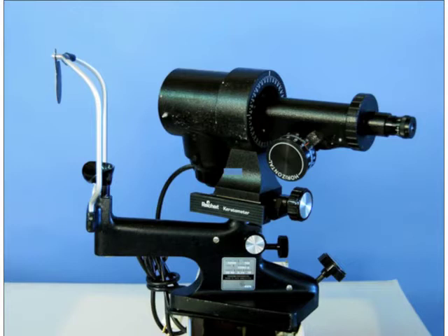Also, if you look at the dials on the keratometer, you'll notice that there are two sets of scales. And I don't mean that one says horizontal, one says vertical. I mean that within each dial, there's a set of scales that'll go from, I don't know, maybe 36 to 49, and those are dioptric readings. And when we talk about the keratometry readings, those are usually the numbers that we're giving.